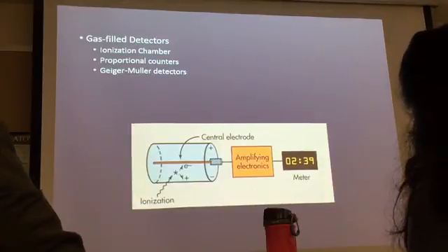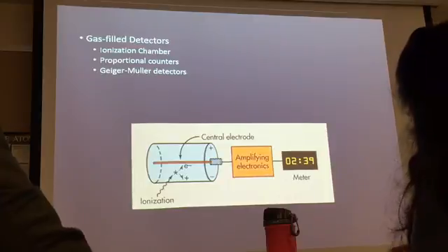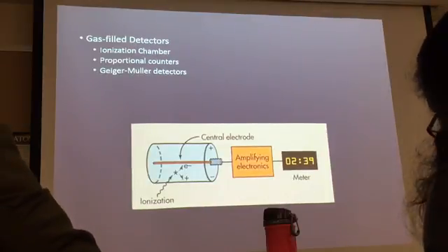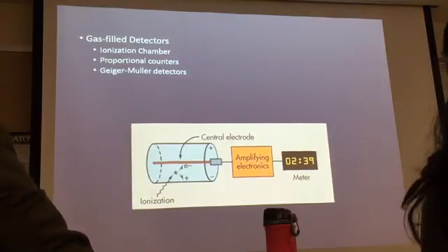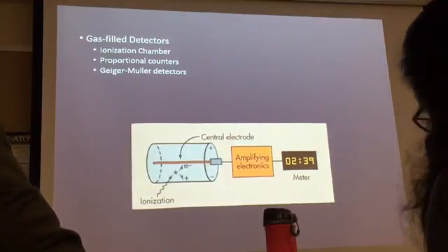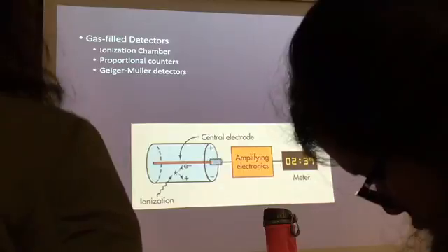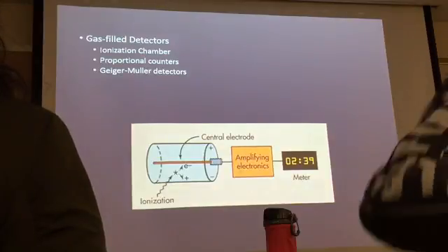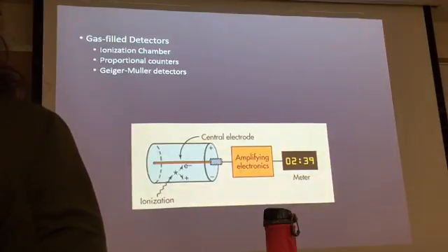Make sense? All right. And in this area here, this is called the recombination area. That's why it's called R. What happens in this area is that if the ion chamber is exposed to radiation, you have the molecules and the ions. You break the molecule, the ions go separate ways, and then boom, they recombine. That's why it's called the recombination area. So you don't get any reading.